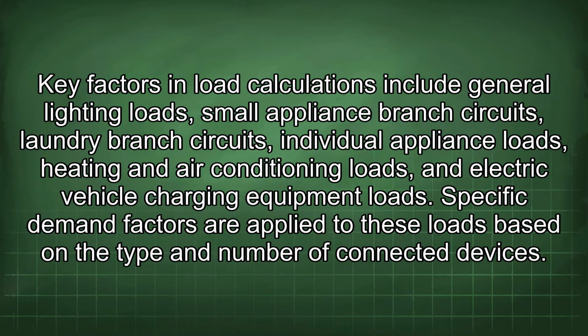Key factors in load calculations include general lighting loads, small appliance branch circuits, laundry branch circuits, individual appliance loads, heating and air conditioning loads, and electric vehicle charging equipment loads. Specific demand factors are applied to these loads based on the type and number of connected devices.